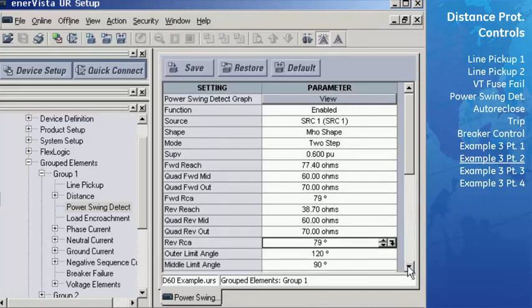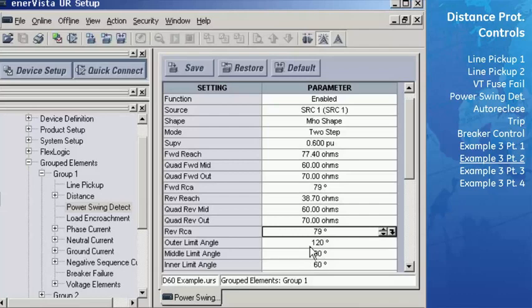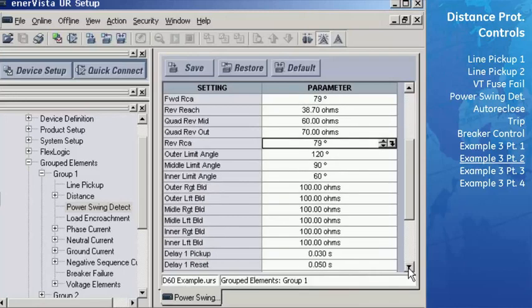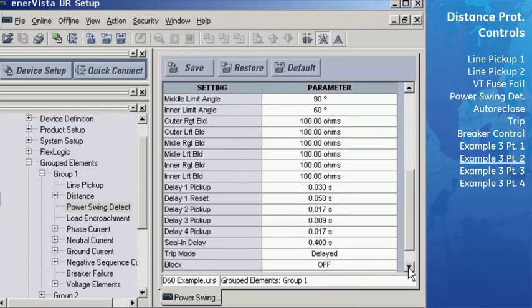Since none of the power swing characteristics are known, we'll leave the outer and inner limit angles as 120 degrees and 60 degrees respectively. Also, leave the delay 1 pickup at 30 milliseconds and delay 1 reset at 50 milliseconds. All the other timers are for out-of-step tripping only and won't be used. Save these settings to the settings file and close this window.